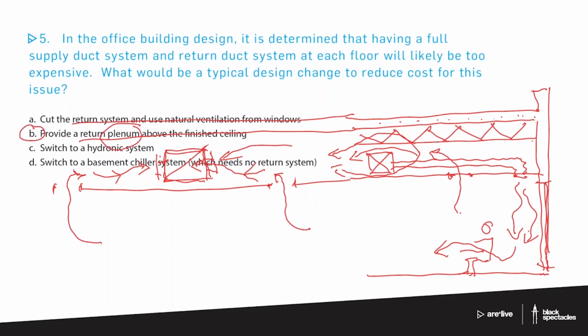So B is the answer. Cutting the return system and natural ventilation from windows is a reasonable answer for a portion, but it's really not believable to have 100% fresh air supply. Maybe with COVID things will change, but I can't imagine it. Switching to a hydronic system is possible, but it's a big change and doesn't get us the air conditioning. And switching to a basement chiller system supposedly needs no return system, but it actually does need one, so that statement is incorrect and D can't be the answer. By far the best answer here is plenum.